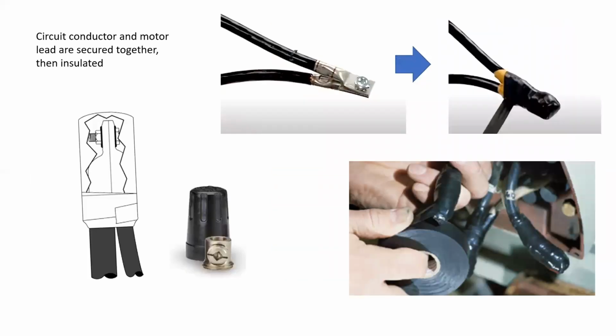Now, the circuit conductor and the motor lead are secured together inside the motor terminal box in a pigtail type of splice. And if it's a very large motor, then we use a compression connection with eyelets and a bolt, and we torque them together, and then we coat the whole thing in insulating tape and then electrical tape. Or you can use Marettes. Sometimes people prefer on the smaller motors to use a set screw type of Marette. And other times there's other brands of proprietary equipment that will allow us to make this connection easily and quickly. Most often what you will see is Marettes for smaller horsepower motors that are then wrapped with electrical tape just to ensure that they don't fall off due to the vibration within the motor.